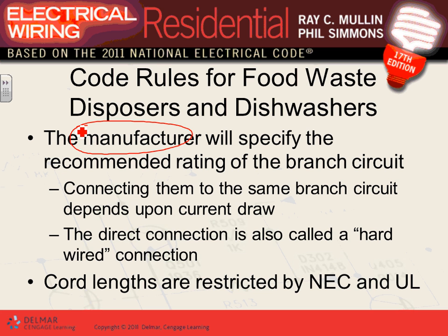So the branch circuit depends on the current. Can I connect two appliances on one branch circuit? Yes. But a good design, when you go commercial, industrial, guys, is a dedicated circuit for all these appliances. If you go to a McDonald's, now we're going commercial, right? A good design, remember, we're not bare minimum. A good design is a dedicated circuit for these appliances. Good design.